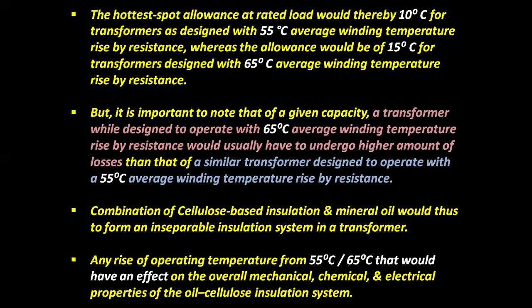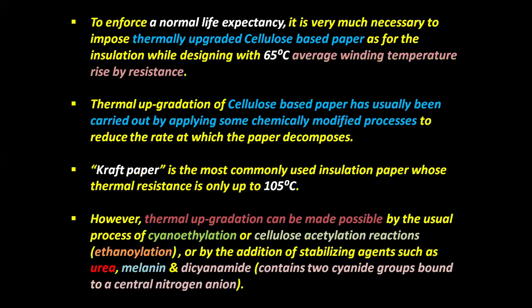The combination of cellulose based insulation and mineral oil forms an inseparable insulation system in a transformer. Any rise of operating temperature from 55 degrees centigrade or 65 degrees centigrade would have an effect on the overall mechanical, chemical, and electrical properties of the oil cellulose insulation system. To ensure a normal life expectancy, it is very necessary to use thermally upgraded cellulose-based paper as insulation when designing with 65 degrees centigrade average winding temperature rise by resistance. Thermal upgradation of cellulose-based paper is usually carried out by applying chemically modified processes to reduce the rate at which the paper decomposes.